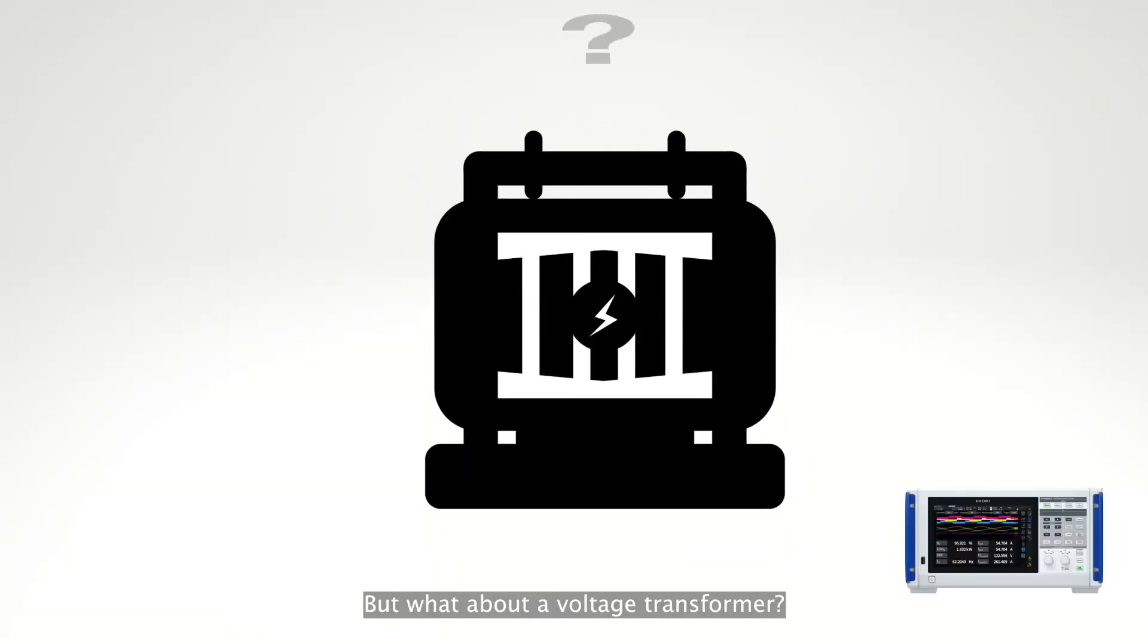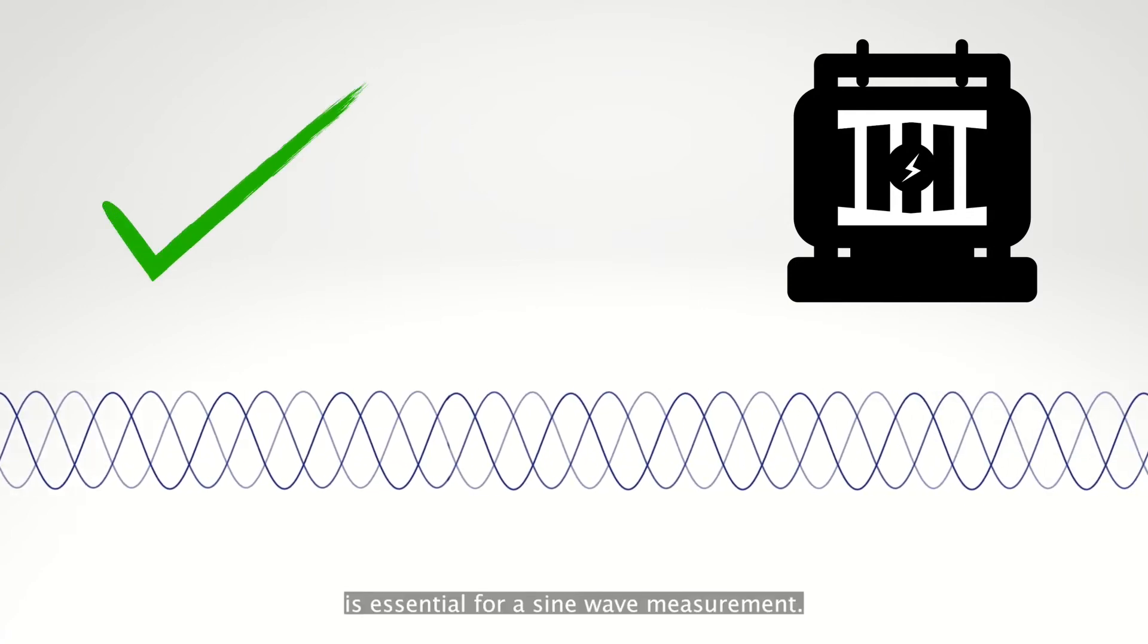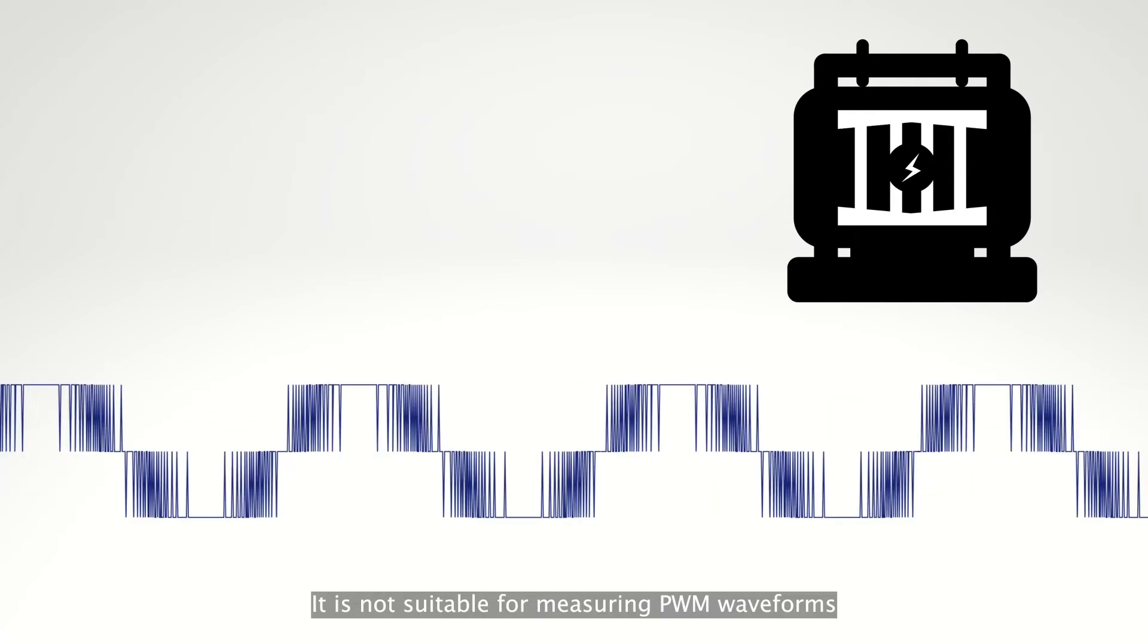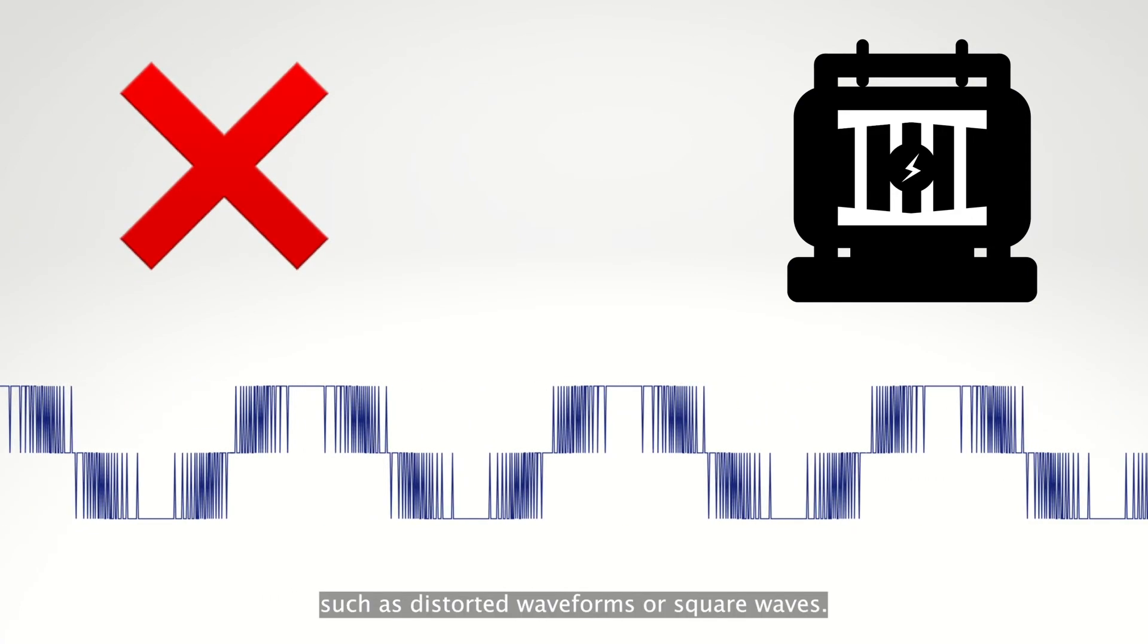But what about a voltage transformer? A voltage transformer, or VT, is essential for a sine wave measurement. It is not suitable for measuring PWM waveforms such as distorted waveforms or square waves.